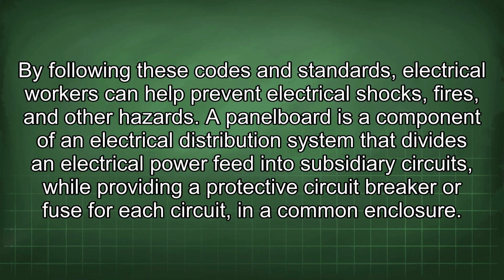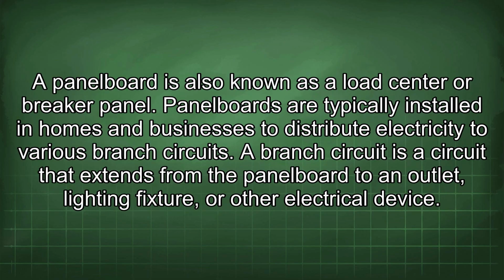A panel board is a component of an electrical distribution system that divides an electrical power feed into subsidiary circuits, while providing a protective circuit breaker or fuse for each circuit in a common enclosure. A panel board is also known as a load center or breaker panel. Panel boards are typically installed in homes and businesses to distribute electricity to various branch circuits. A branch circuit is a circuit that extends from the panel board to an outlet, lighting fixture, or other electrical device.